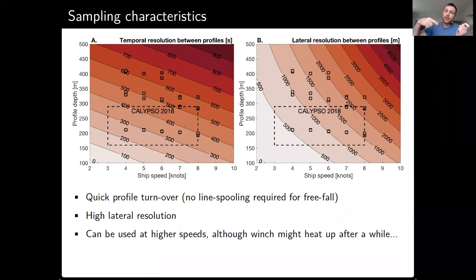You had to spool line at the back of it, so you had to put it back on deck, spool line on the tail spool, and redeploy it. That would make the temporal resolution very long, which means the lateral resolution would suffer from it. But because the EcoCTD is heavier, you don't need to do that. You bring it back to the ship, and by the time you see it show up at the surface, you release it again, and you don't have to bring it back up and then redeploy it.